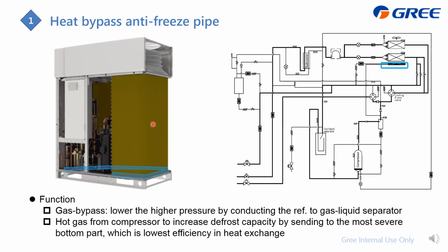the ice will become water and flow down, and easily accumulate at the bottom, which is this blue area. And when we go back to heating, the lower side always becomes the coldest, which means the accumulated water will also become ice easily, right? So in summary, the heat transfer efficiency will be very poor, and at the defrost it will also deteriorate or worsen.